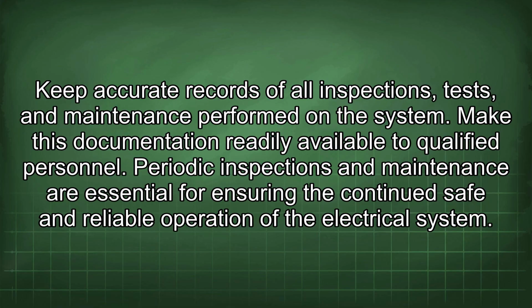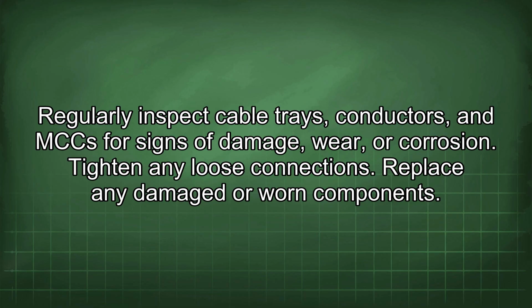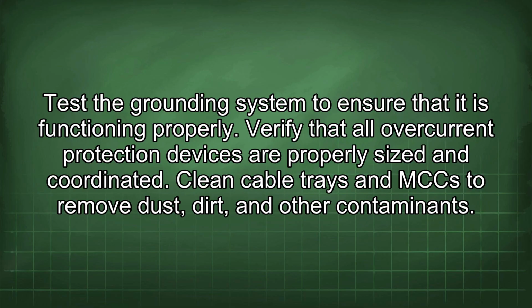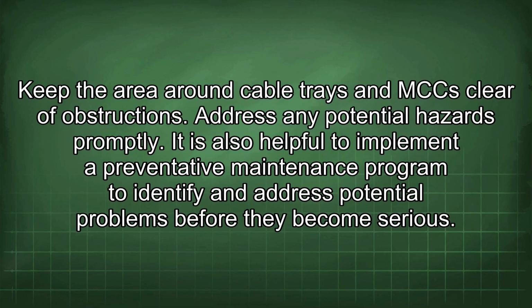Periodic inspections and maintenance are essential for ensuring the continued safe and reliable operation of the electrical system. Regularly inspect cable trays, conductors, and MCC for signs of damage, wear, or corrosion. Tighten any loose connections. Replace any damaged or worn components. Test the grounding system to ensure that it is functioning properly. Verify that all overcurrent protection devices are properly sized and coordinated. Clean cable trays and MCC to remove dust, dirt, and other contaminants. Keep the area around cable trays and MCC clear of obstructions. Address any potential hazards promptly.